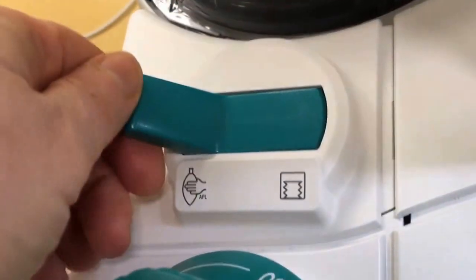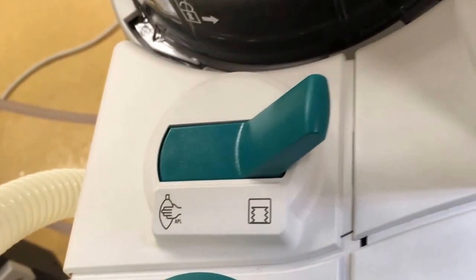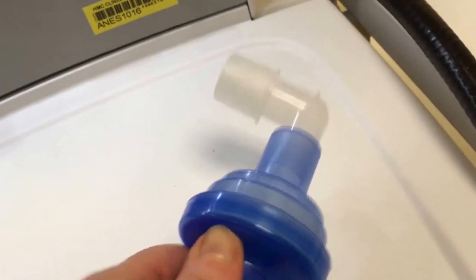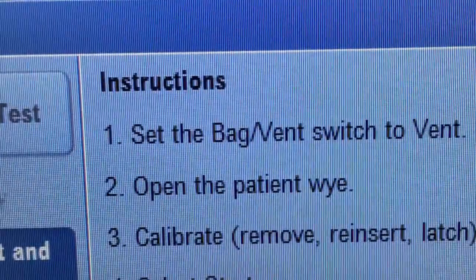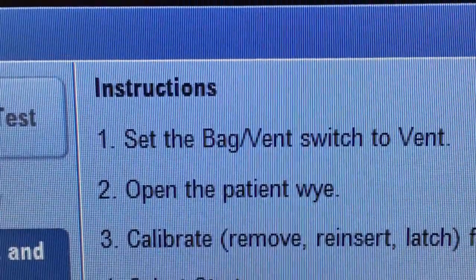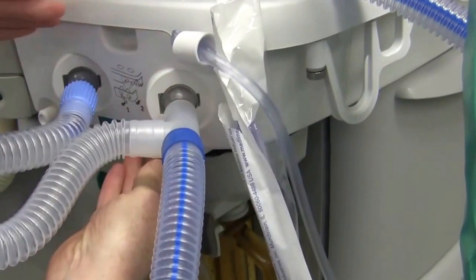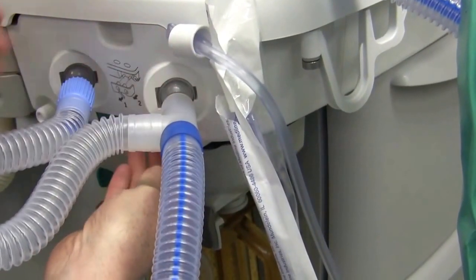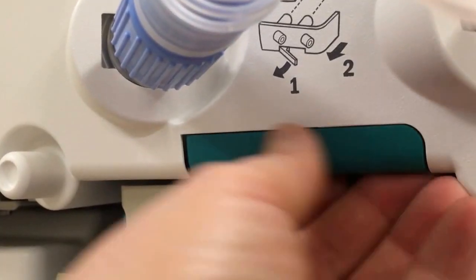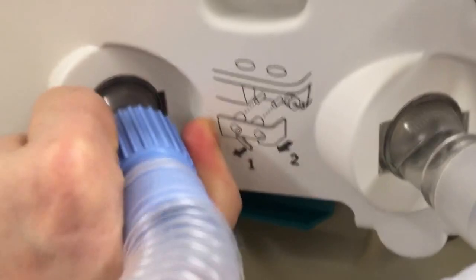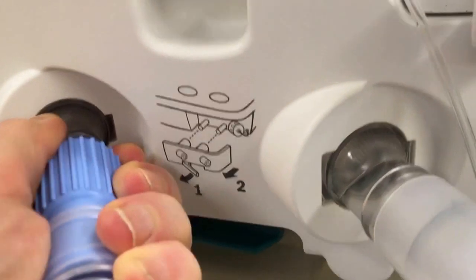First, you're going to set the bag vent switch. The next step says leave the patient Y open. The next step says calibrate the flow sensor. You come over here with your inspiratory and expiratory limbs, and right underneath that is a green lever that you pull out, and you wiggle the whole module out only part way.